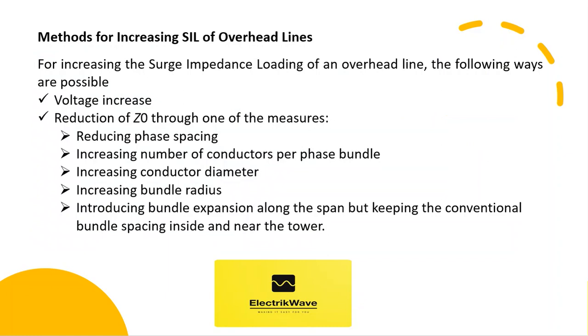Now let's see methods for increasing SIL of overhead lines. For increasing the surge impedance loading of an overhead line, the following ways are possible. Voltage increase, or reduction of Z0 through one of the measures: reducing phase spacing, increasing number of conductors per phase bundle, increasing conductor diameter, increasing bundle radius, introducing bundle expansion along the span, but keeping the conventional bundle spacing inside and near the tower.